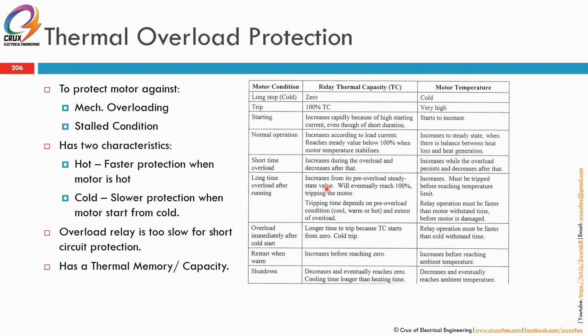For long time overload after running, it increases from its pre-overload steady state value and eventually it will reach 100% thermal capacity. And tripping time will depend on the pre-overload condition, whether it was running 50% or 80% load before the overload condition happened. So the motor temperature will increase and must trip before reaching its temperature limit. This will mostly depend on the temperature class of the winding.